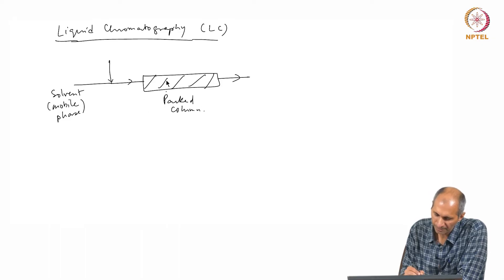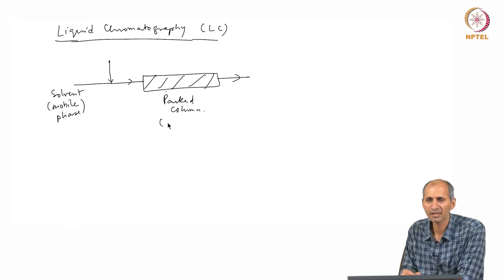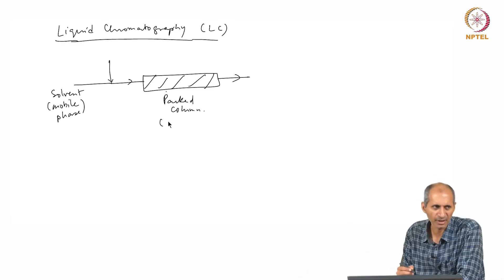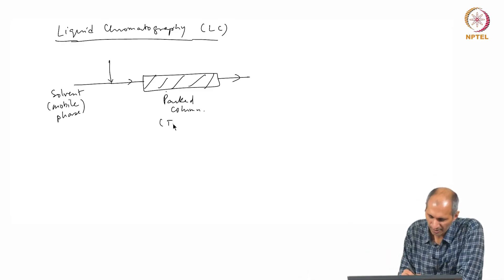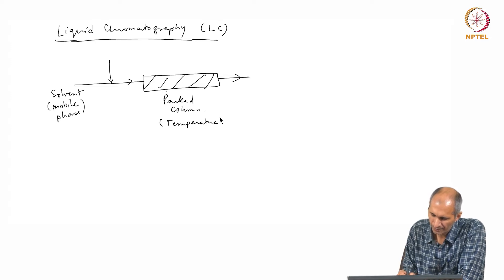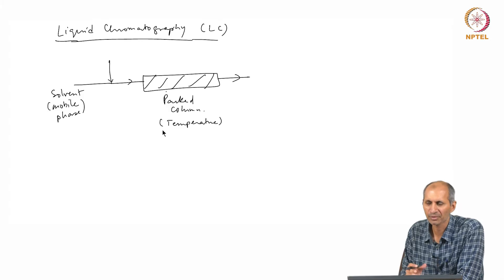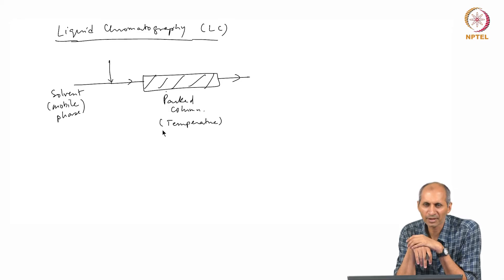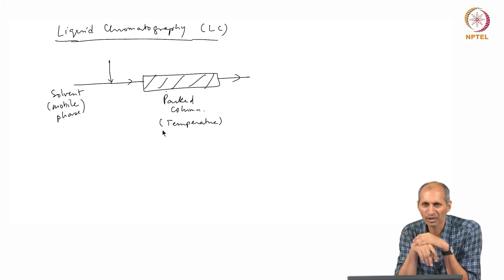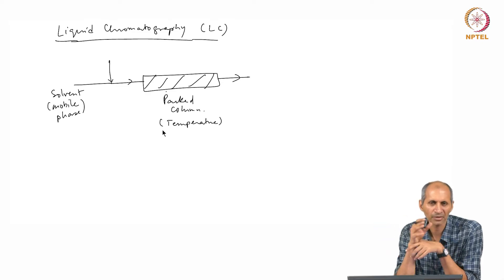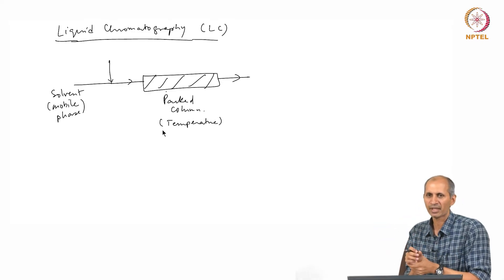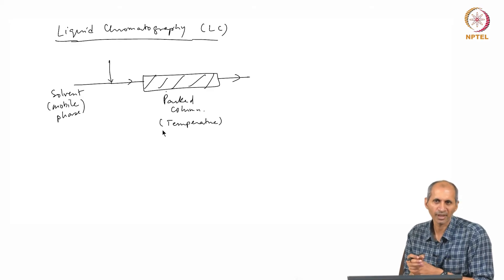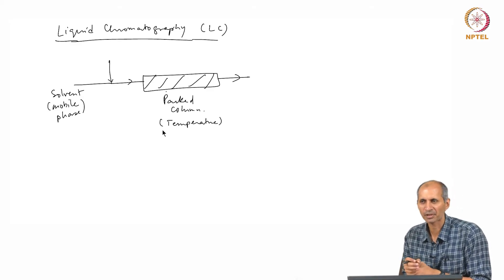You can change the temperature, but you cannot change it in the range of a GC. Temperature control is usually not done. The reason we do not do it is there is a liquid inside. If you increase temperature too much, it will start boiling and it will vaporize and that will create a bubble and that bubble stuck in the column is a problem. Flow will not occur properly.